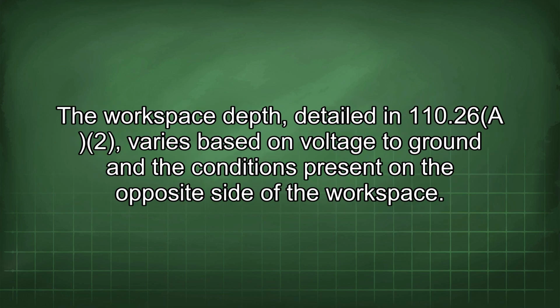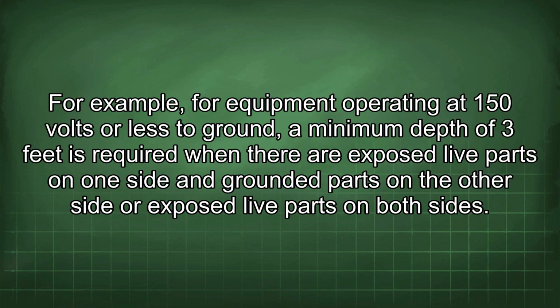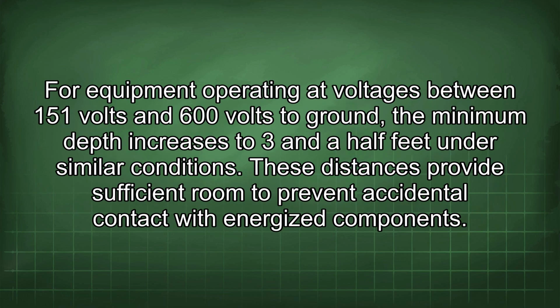The workspace depth, detailed in 110.26(A)(1), varies based on voltage to ground and the conditions present on the opposite side of the workspace. For example, for equipment operating at 150 volts or less to ground, a minimum depth of 3 feet is required when there are exposed live parts on one side and grounded parts on the other side, or exposed live parts on both sides. For equipment operating at voltages between 151 volts and 600 volts to ground, the minimum depth increases to 3.5 feet under similar conditions. These distances provide sufficient room to prevent accidental contact with energized components.